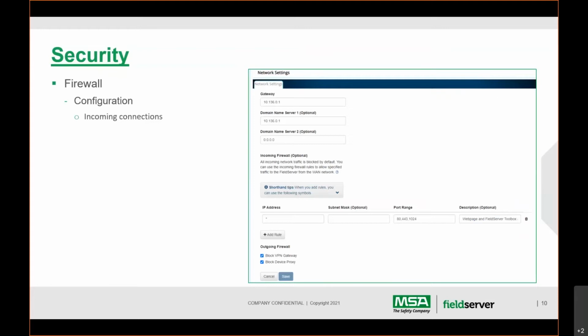Another example could be, you know, if you had Modbus TCP/IP, you'd put the port range in of 502, and you might have a specific IP address as well. You could have BACnet IP, 47808 is the port number for that, or sometimes they use 809, so it'll allow that connection in. And then once that is the routing setup, you can also have the ability to block VPN connections coming in and proxy tunnels. So it just gives people an extra bit of security, because on all FieldServer bridges, we do have the ability to connect via VPN, and it can be blocked if required. So we're giving the end users a lot of configuration options for routing and for firewall.